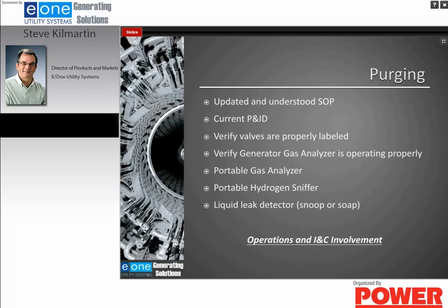I would also recommend that you have a portable hydrogen sniffer, because some of the valves that you're going to be turning during this purging process haven't been exercised for, again, 5, 7, 10 years. And the packing could have dried, so you need to make sure that the piping, the valves, and the fittings that you're working with have no hydrogen leaks, and therefore I would recommend the use of a portable hydrogen sniffer. If you cannot get a portable hydrogen sniffer, at the very least you should have a liquid leak detector to detect any potential leaks.